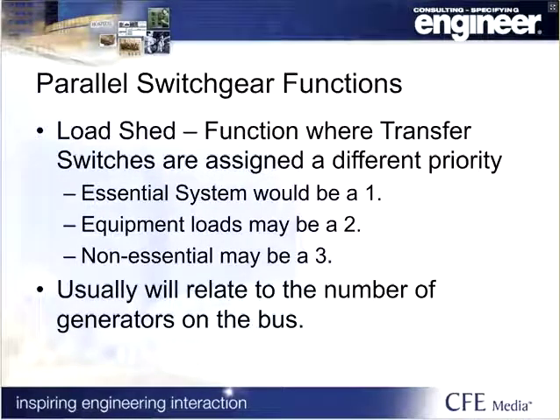So the first one is load shed. Load shed basically would be if I have a system where I've got my critical life safety equipment branches, and then I've got another branch that serves maybe an MRI or maybe a group of elevators, and then maybe I have a final branch that serves just normal power throughout the building.